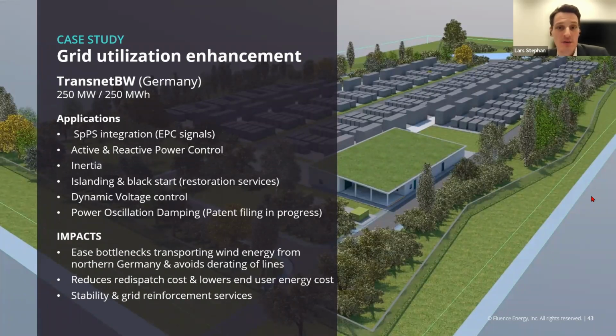Going forward, we see those assets being able to provide things like inertia, dynamic voltage control, power oscillation dampening. So a lot of things those assets can do. Many of those products don't exist yet today, but we know that as we move away from rotating masses, inertia from synchronous machines in the grid, to an inverter-based power system, we will need new ways to provide system inertia, system stability services, black start capability, for example. And these are things that those assets are already able to do.